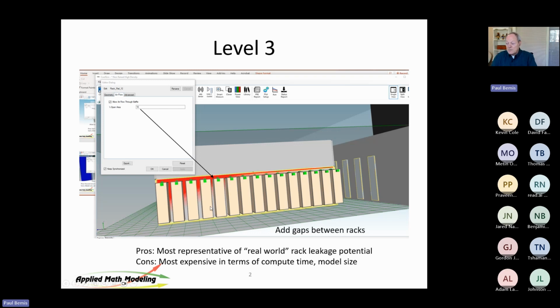So here what we've done is simply take the racks, put a gap between them of 6 inches, 3 for either side, get them up off the floor a little bit, make them not quite as wide. Remember, it's the server that we're trying to model here, not the rack. We really don't care about the rack itself. We care about the inlet of the server. So we give it 3 inches on either side, 3 underneath, 3 on top is good, and then put that leakage parameter in there at 10%. This is really fast to do. It's easy to do. We've just recently modified the software to make this even easier to do, and you can bang these things out quick.